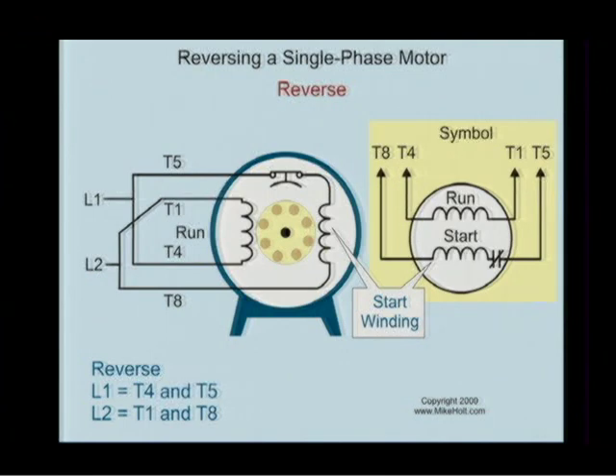And that's where you take your drum switch. Now, a drum switch would have a truth table on it, wouldn't it? It would tell me that in this state you have no contacts closed. But if you go in this direction, then this goes to here, and this goes to here, and it goes to there. But if you go over here, those two and those two are the same, but now we've reversed two of the leads out of the four, and it causes the motor to go in reverse. I wish I had a drum switch in there, and we'll add a drum switch in the textbook. So Mike will pick that up and add a drum switch so you can see how it switches. Now this is a single voltage motor.